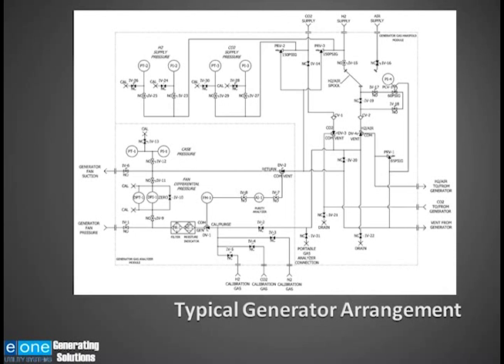And another important note here is this line at the bottom of the page. It's called a cal purge, the three-way valve. When we're purging the generator, that three-way valve is changed so that the line that's feeding the analyzer is coming from the vent of the manifold, so that we're monitoring the gas that's leaving the generator, not taking a sample from the fan differential pressure or suction lines.